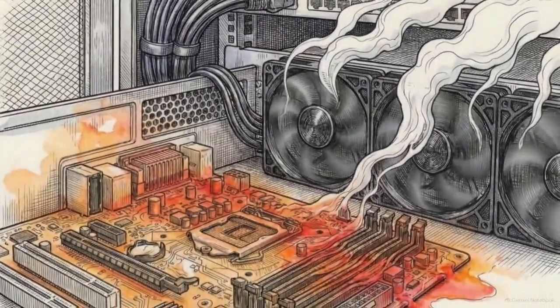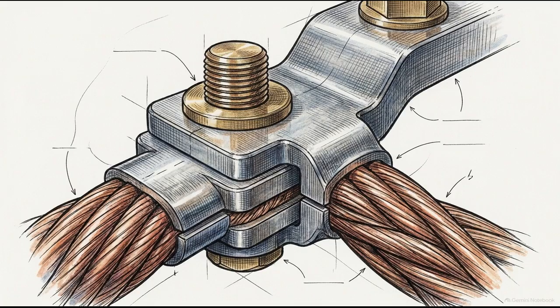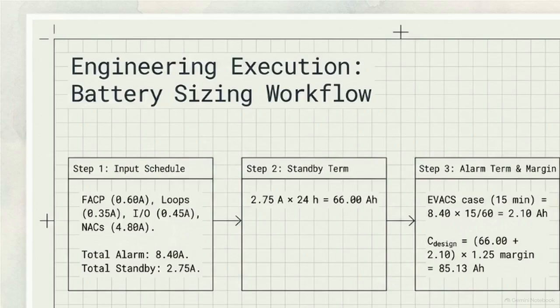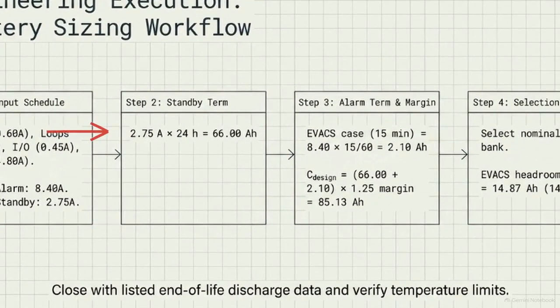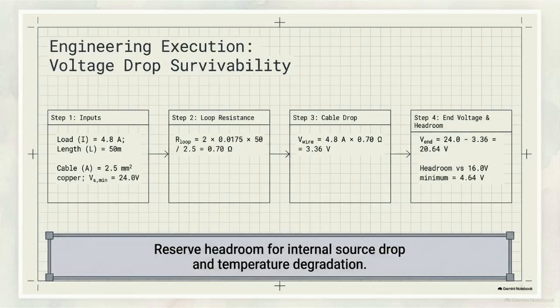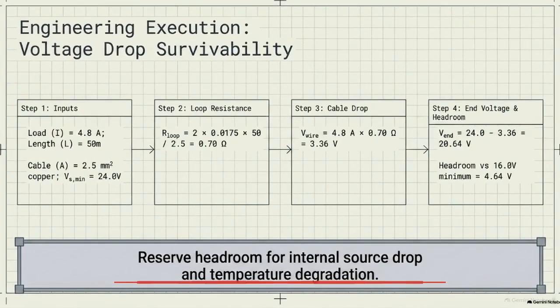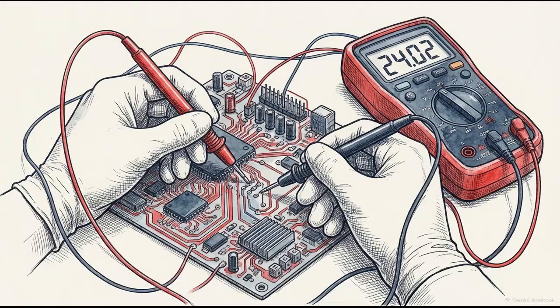Digital logic is only as reliable as the physical copper and batteries supporting it during an outage. This workflow shows the mathematical rigor to size standby power. It calculates a mandatory 24-hour standby term, and in Step 3 accounts for a 15-minute high-load voice evacuation state, plus a 25% safety margin. Voltage drop is a constant threat. Step 4 proves a 24-volt supply can drop to 20.6 volts over a 50-meter loop. Engineers must reserve headroom against the 16-volt minimum to survive temperature degradation and source drops over time. Reliability requires extreme precision in the analog electrical calculations that keep the sensors and notification devices alive.